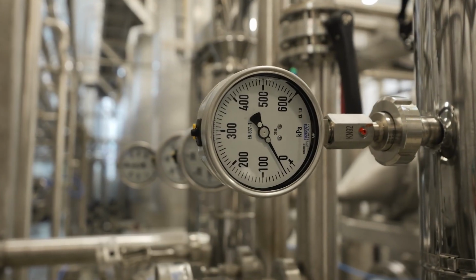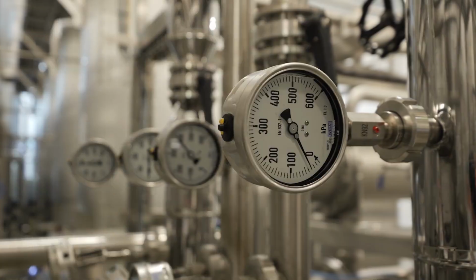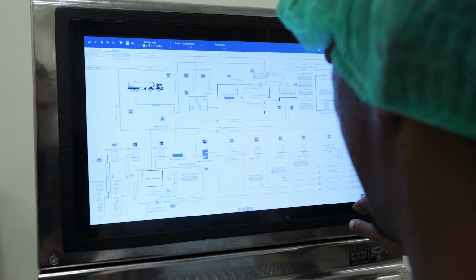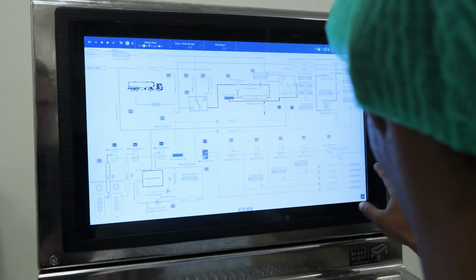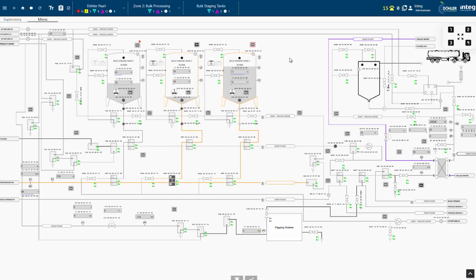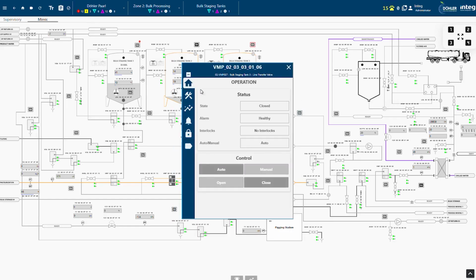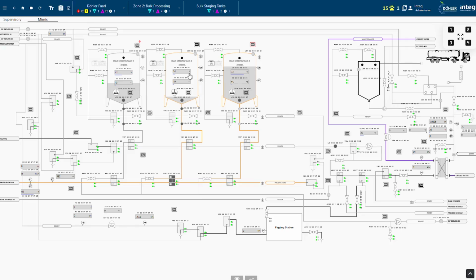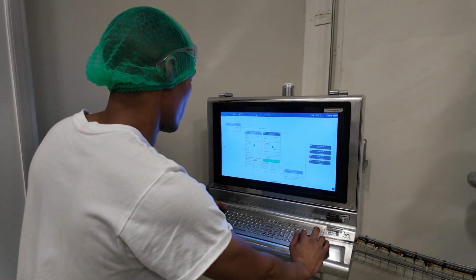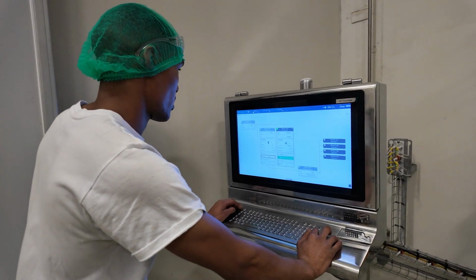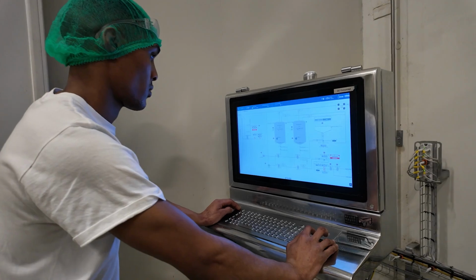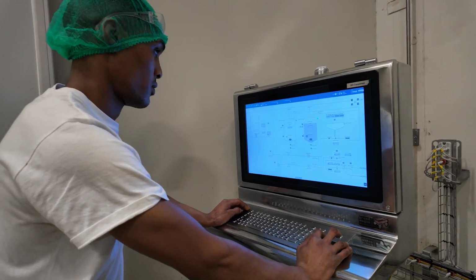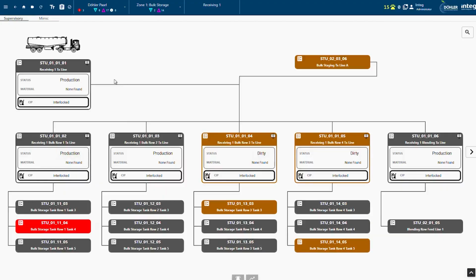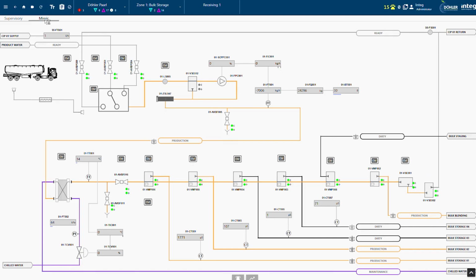There's so much equipment on this plant that we toned down the HMI look so that only when a specific event occurs needing the operator's attention, it pops up and the operator can react immediately. Only alarms on lines that are in process would activate, pop up on screen, and alert the operators. We have mimic screens, overview screens, and representative P&ID screens.